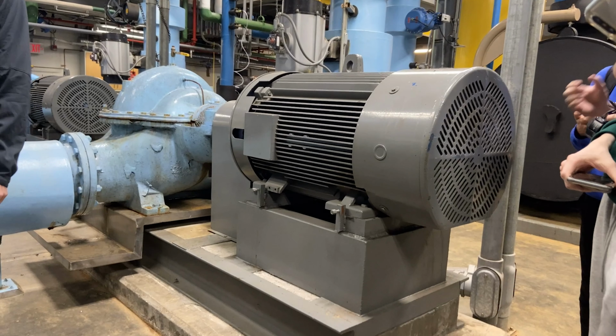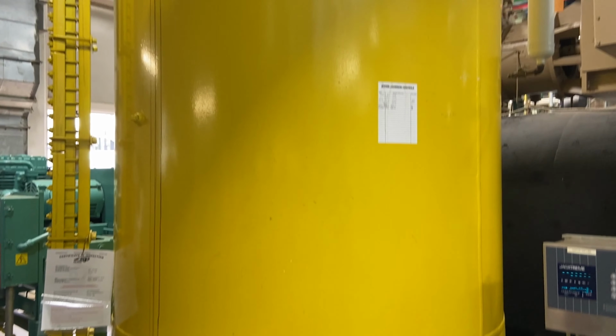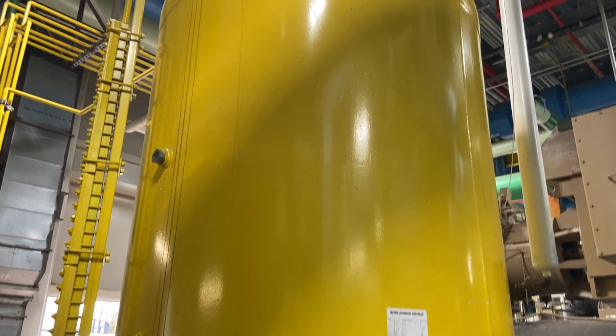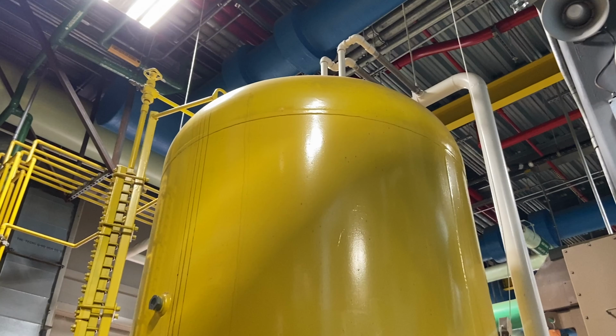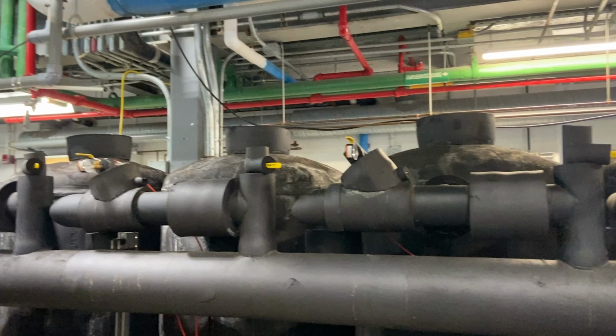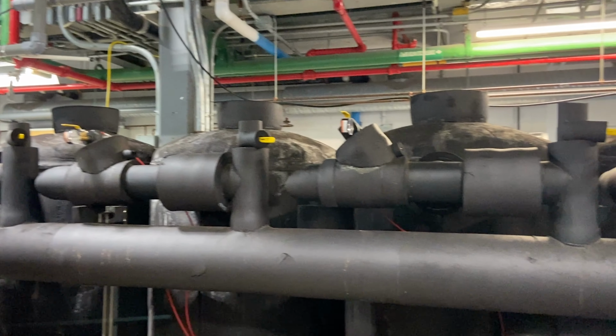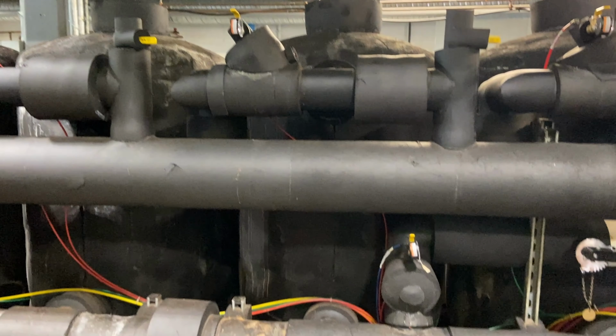What would happen if we didn't treat the water? Well, in this case, power consumption would increase, there would be a lack of heat transfer, corrosion, fouling, and microbiological growth would form, and overall, we would be unable to cool campus. Here at UNC, we have a commitment to sustainability. With 97.5% of the world's water being salt water, there's a limitation of fresh water that we must deal with. One important way this is fulfilled is with the use of reclaimed water.